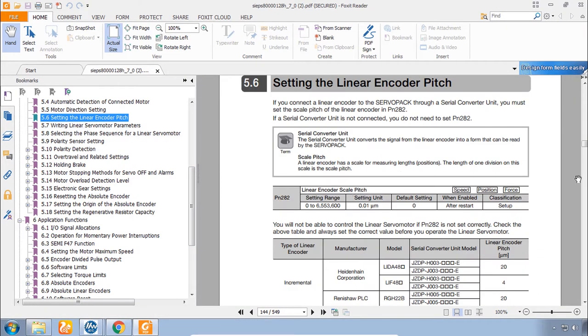With a linear motor you have a linear scale. With lines appearing every certain number of microns. So here we have the setting for that linear encoder scale pitch. In our tuning lab we do have a linear motor. And to use that station you need to set the linear encoder scale pitch. For Yaskawa 20 micron is pretty common. 20 micron scale pitch a setting of 2000.